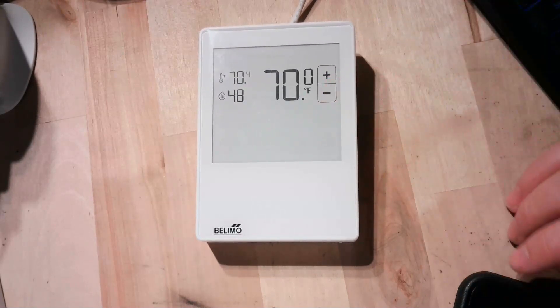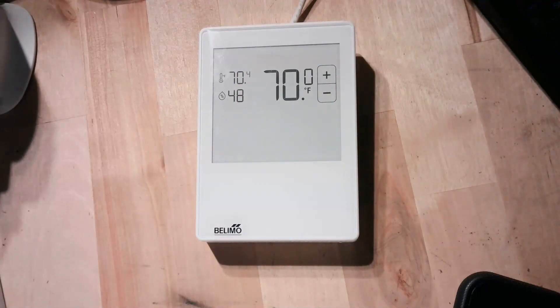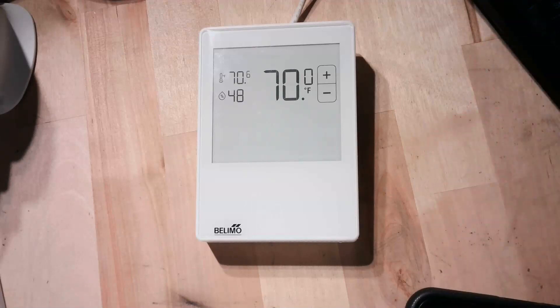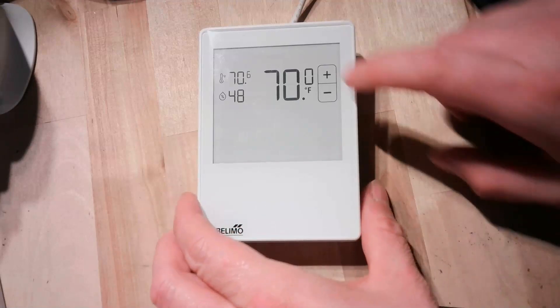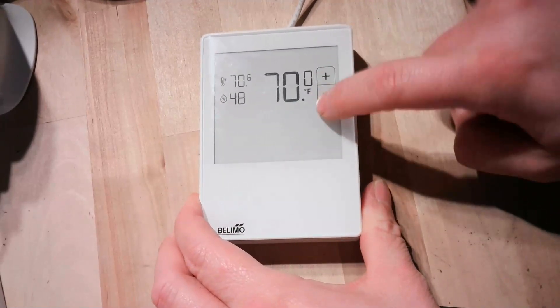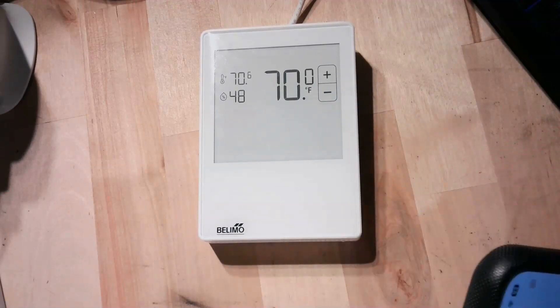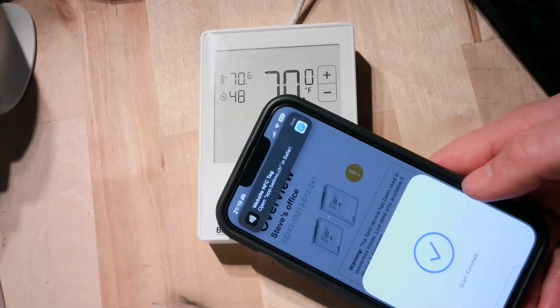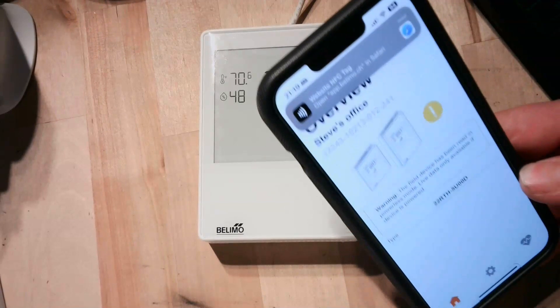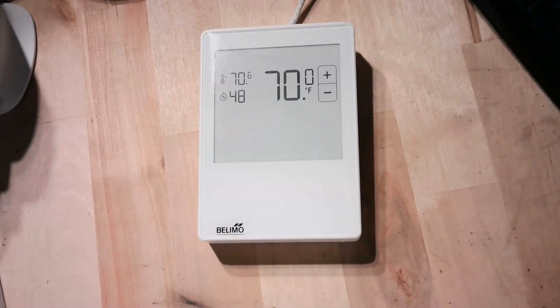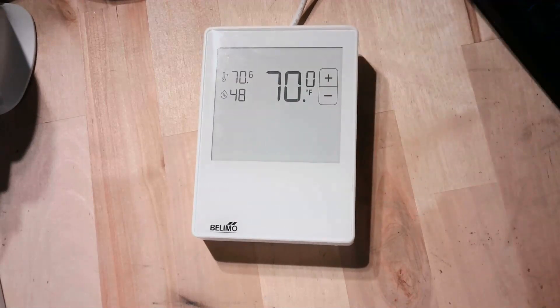There is kind of a drawback to it. I'm going to kill the power to this stat — this stat has no power right now, I've killed the transformer to it. Being an e-paper display, it's going to maintain all of this without any power on it. And if I go to my Belimo app and try to scan something, it's telling me it's offline — powerless mode. That's going to make it a little bit harder to troubleshoot: walking into an office, looking at a stat, seeing something on it, and saying, oh yeah, the unit's on. Well, now you have to actually verify that the unit's on. So that could be a down point for someone.